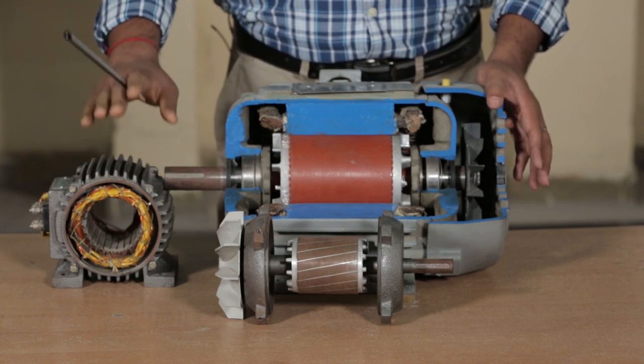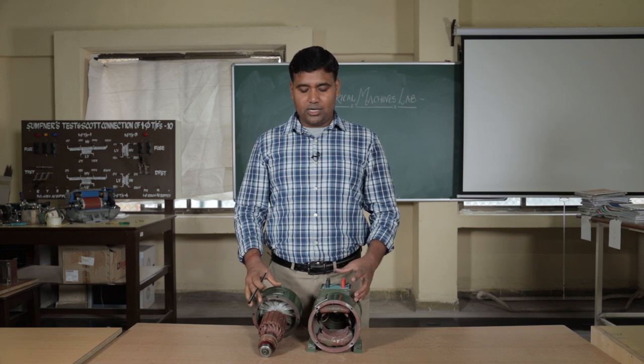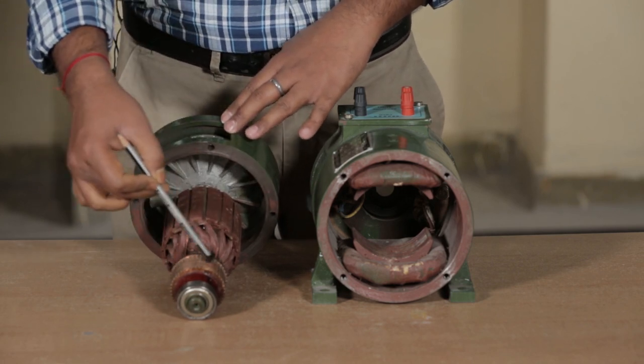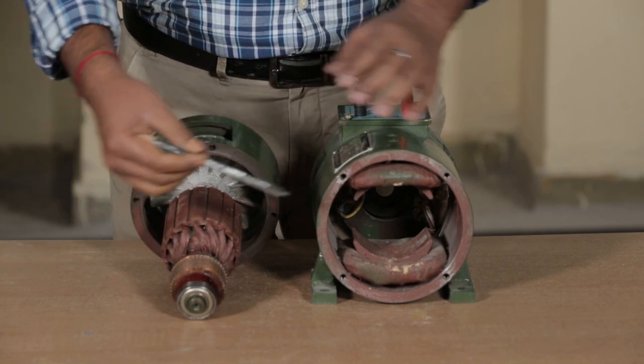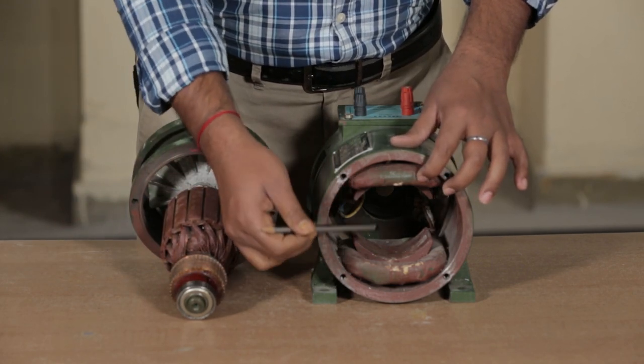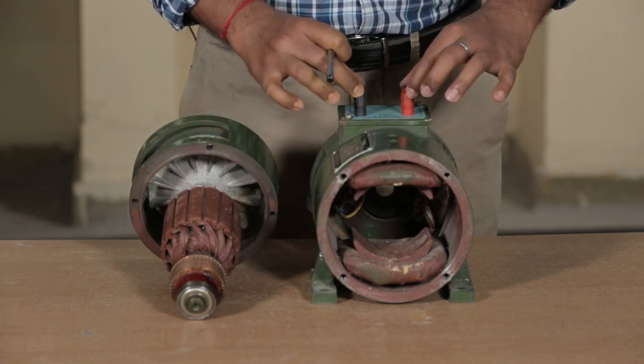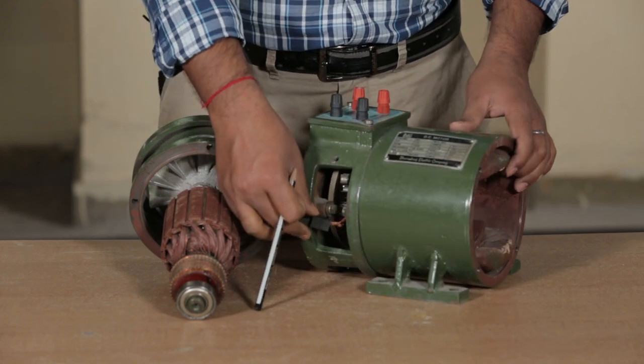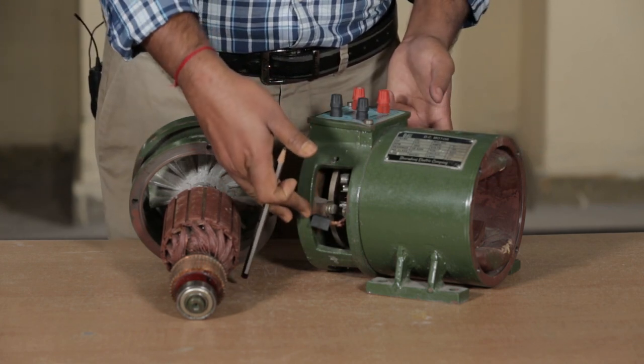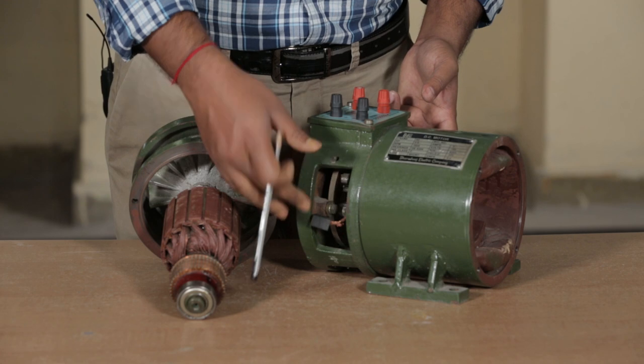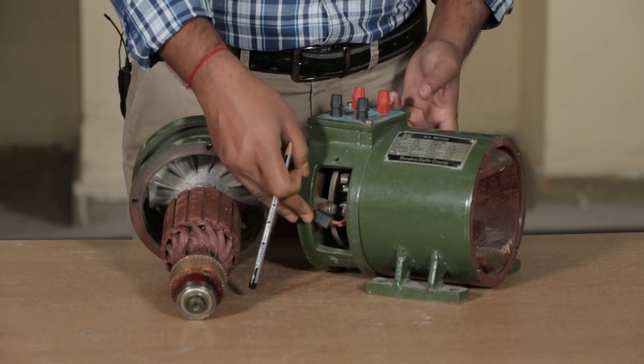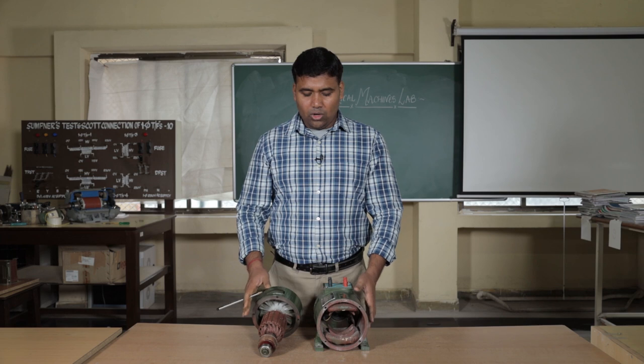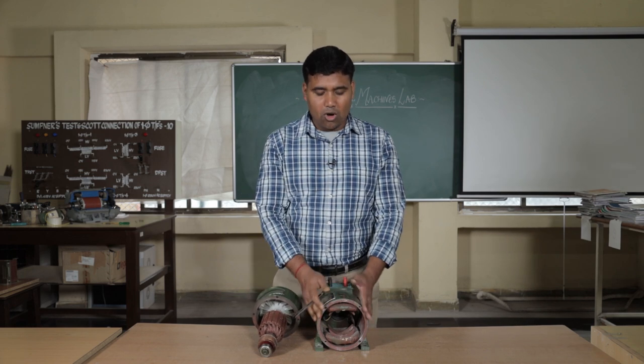Let us see the cutout section of a DC motor. In the DC motor, we have an armature, a commutator, bearings, and field poles — two field poles are there. Terminals come out: this is the armature terminal and this is the field terminal. We can see there are carbon brushes; two brushes are attached to the armature. There will be a voltage loss of two volts per brush drop. This is the yoke of the machine.